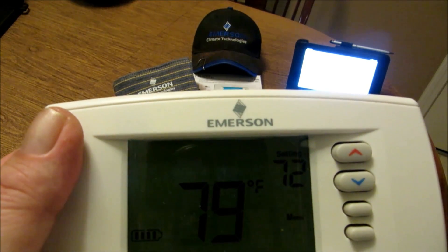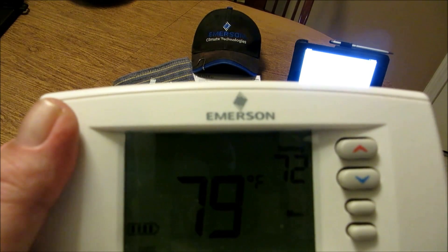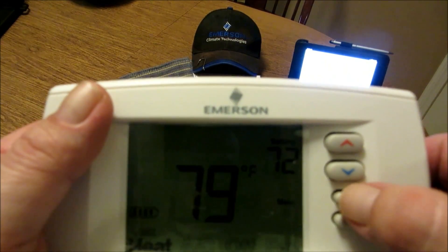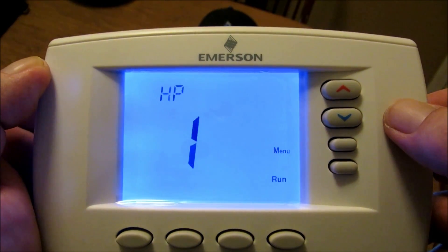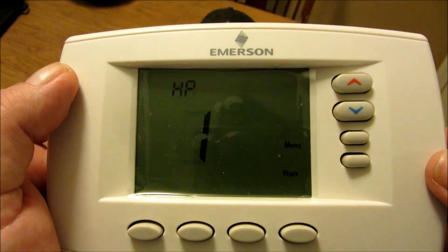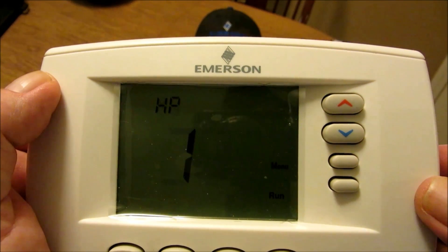Let's get to configuring our brand new White-Rodgers Emerson Climate Technology Blue Easy Reader Thermostat. We'll hit the menu button and now we are at the configuration menu. Number one: this control can be configured for MS2 (multi-stage systems, no heat pump), HP1 (heat pump with one stage of compressor, gas or electric backup), HP2 (heat pump with two-stage compressor or two-compressor systems, gas or electric backup), or SS1 (single-stage system). We chose HP1 — heat pump with one stage of compressor, gas or electric backup.